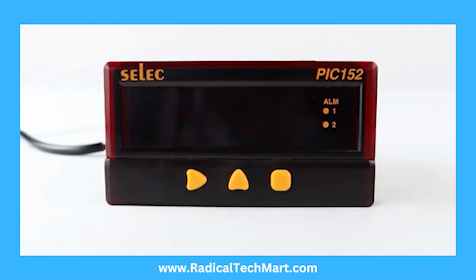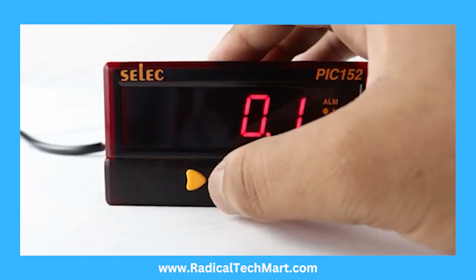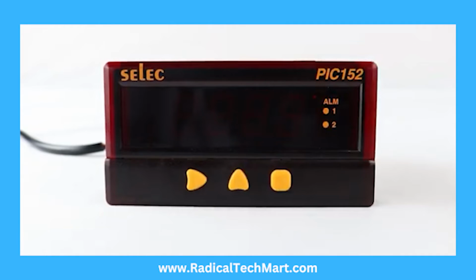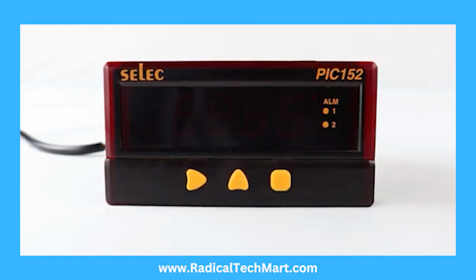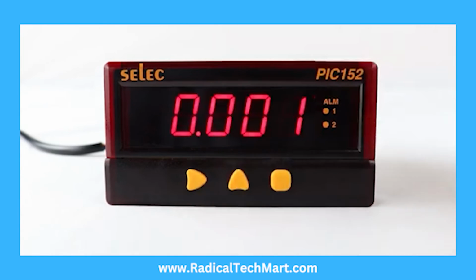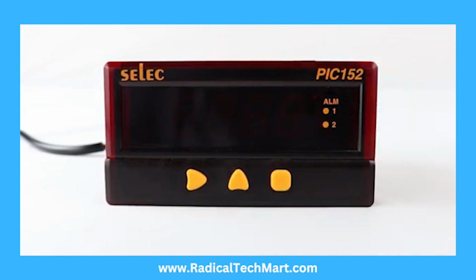Then press the square key to select resolution, which is selectable between 1 and 0.1 for thermocouple and, in case of analog input, among 0.1, 0.01 and 0.001 by pressing the up arrow key, then press the square key.